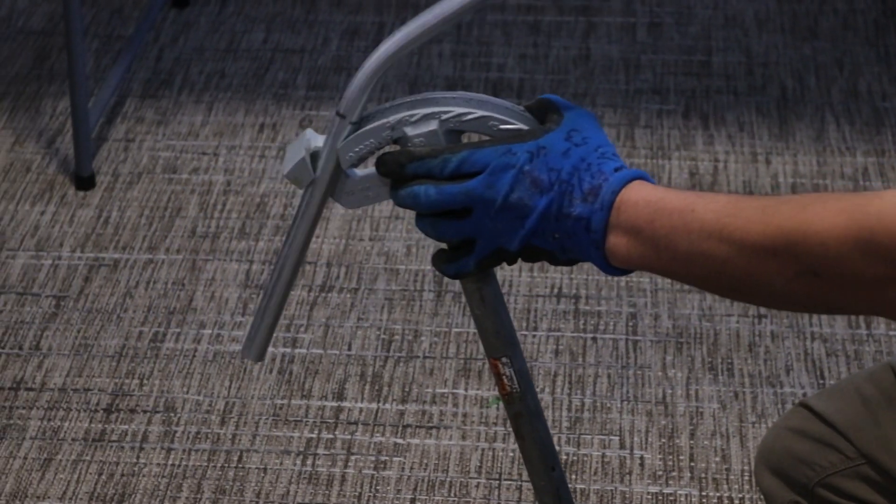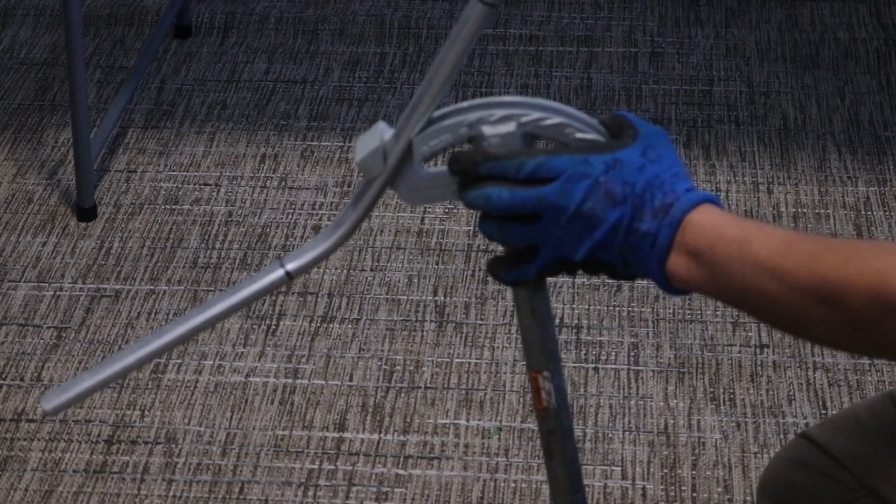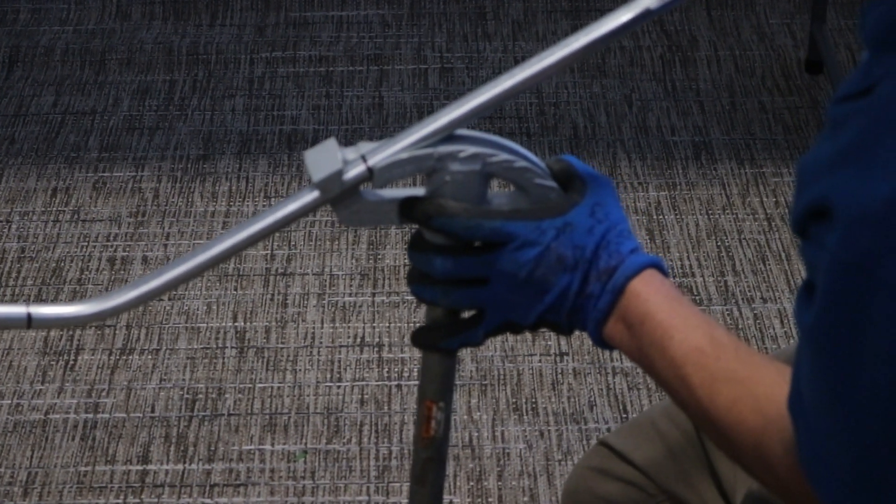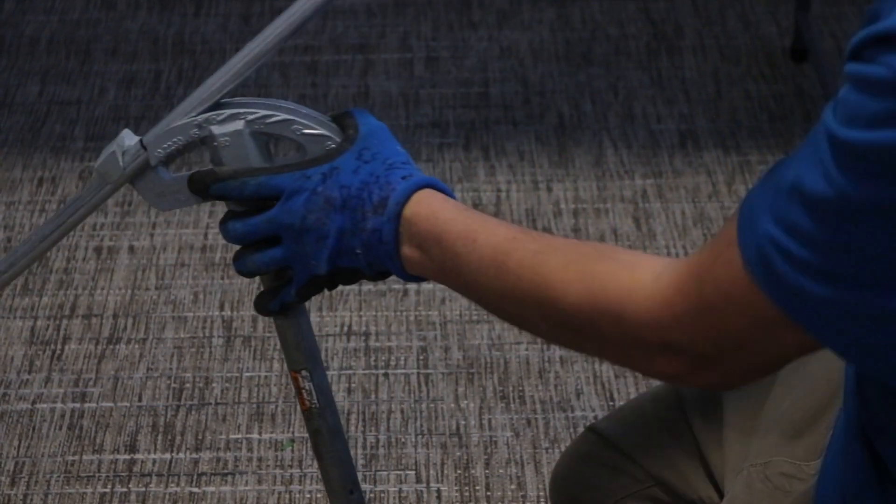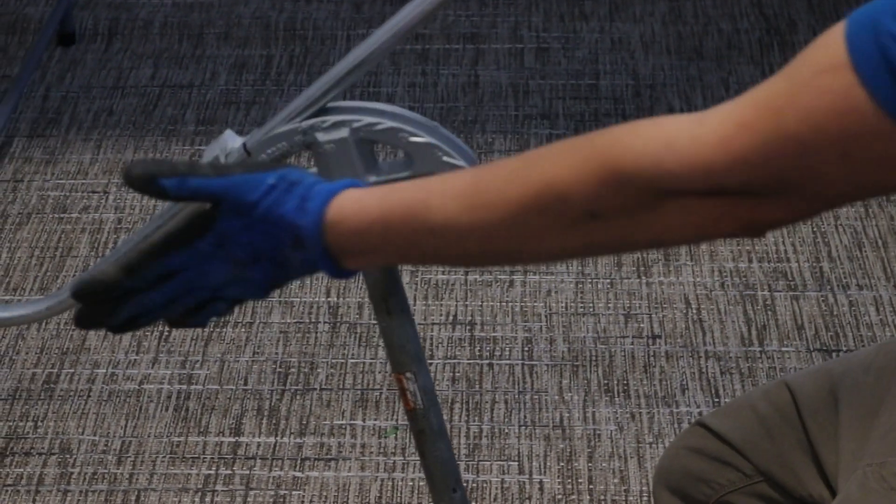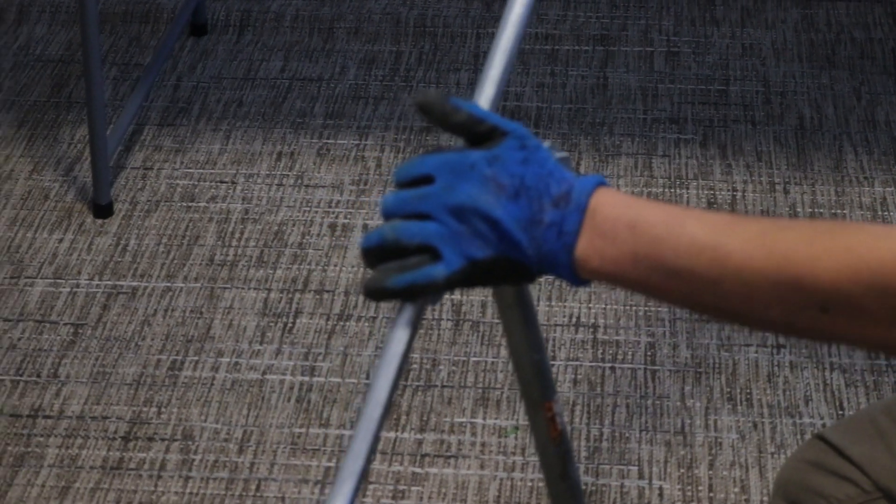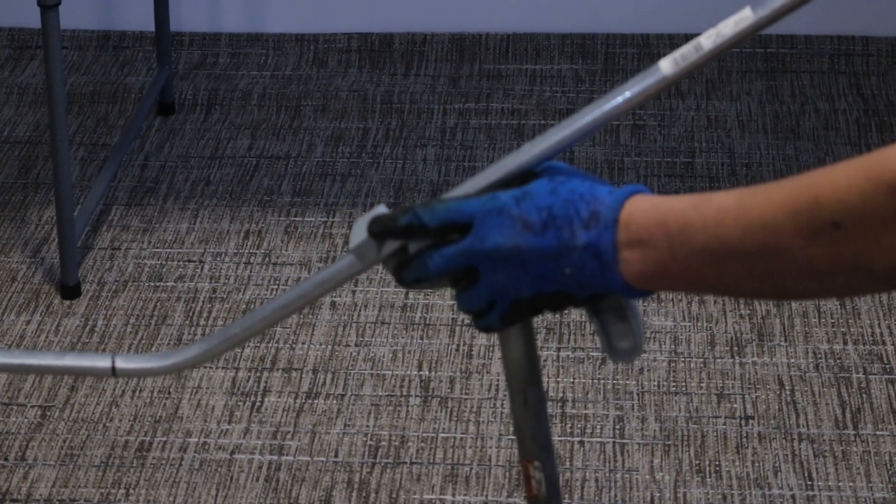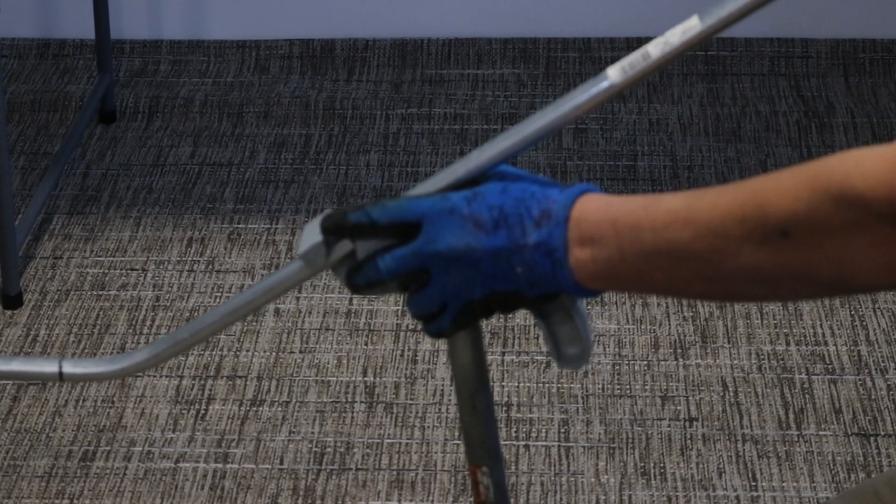I'm gonna take it off and twist my pipe, and then I will go again on my arrow marks. That's my arrow here, exactly. Very important: I have to see if I don't have a dog leg. So dog leg means this conduit must be straight. I'll just double check it. Yeah, this is kind of straight here, exactly straight.